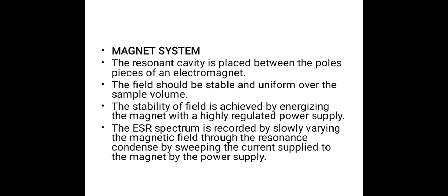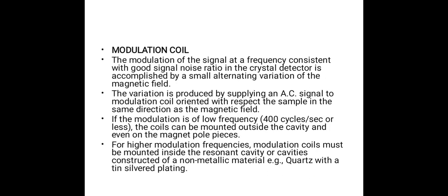The resonant cavity is placed between the pole pieces of an electromagnet. The field should be stable and uniform over the sample volume. Stability of field is achieved by energizing the magnet with a highly regulated power supply. The ESR spectrum is recorded by slowly varying the magnetic field through the resonance condition by sweeping the current applied to the magnet by the power supply.